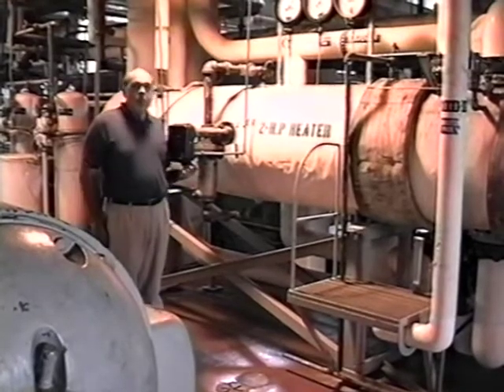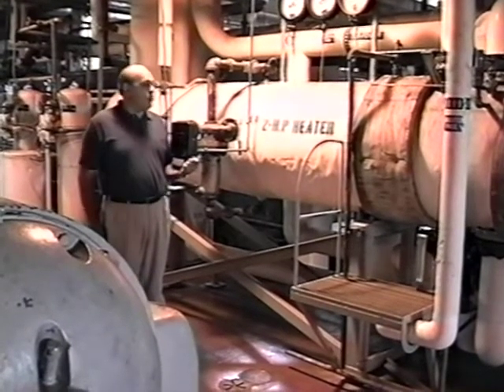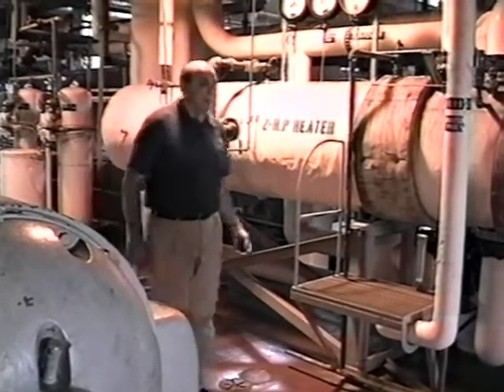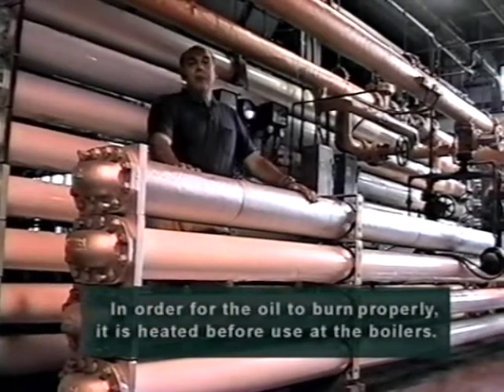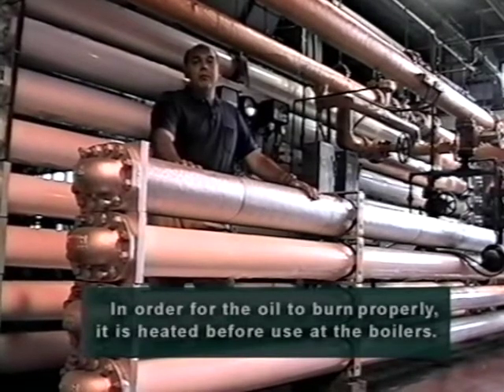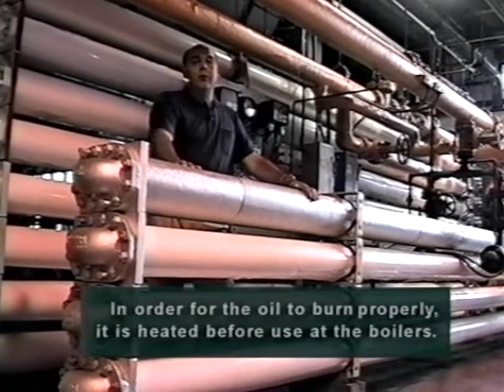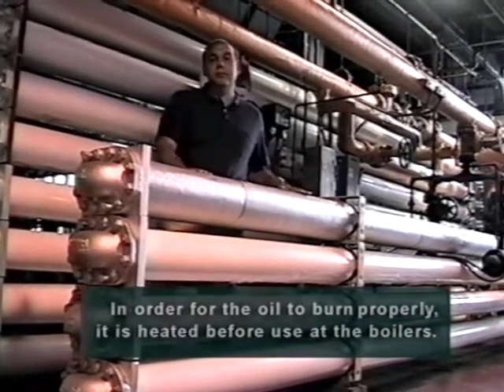This is the number two HP heater, high pressure feed water heater. In order to obtain proper atomization at the burner tips, we need to heat the fuel, and we do that with these fuel oil heaters.